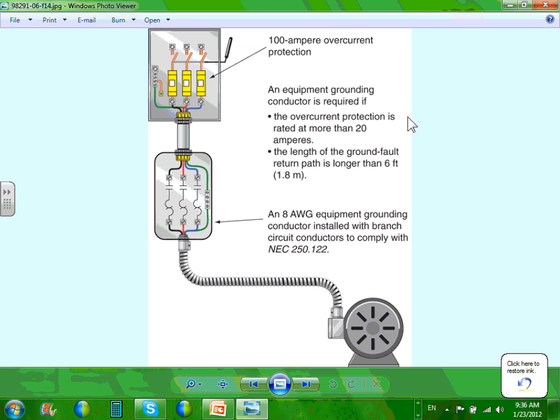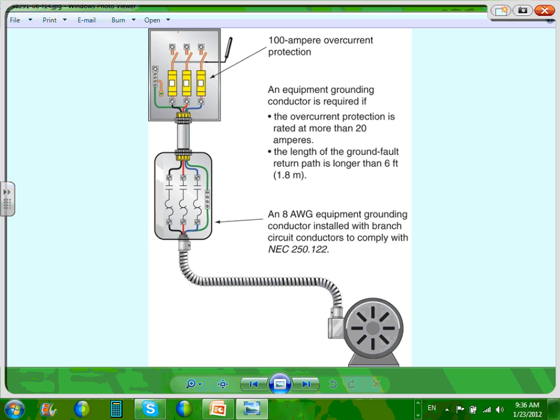Here's a very good example of how you come up with an EMT conduit. You come up with an EMT conduit at the top, going all over here to the service, right? You put your disconnect here, the controller, and you feed. When you come to the controller, it's not a good idea at all to go EMT from here to the motor. You would never do that. So you go to the flex.